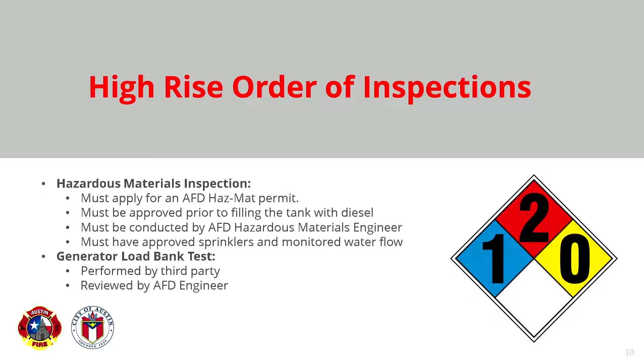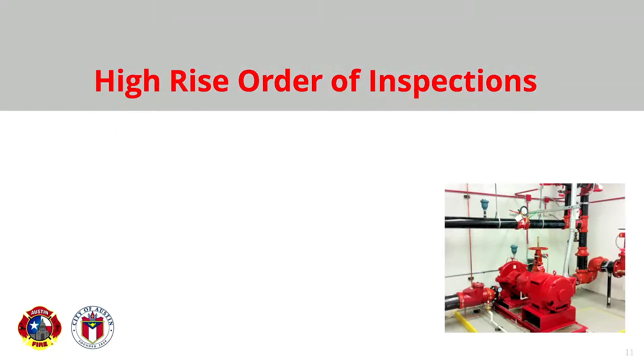So there's the generator load bank test. That's going to take place by a third party. Once you get that load bank test, forward it to your inspector. The inspector is going to forward it to an AFD engineer for review. And once you have the load bank test and it's been approved by an AFD engineer, then we can schedule your fire pump acceptance test. It will not be scheduled until the load bank tests have been reviewed, as I said earlier.